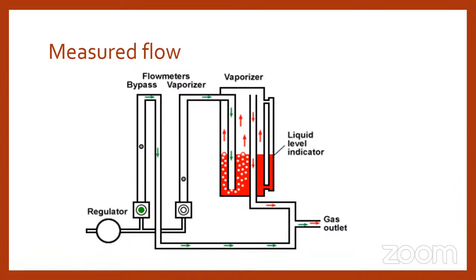So when we open this green knob, as you can see in the picture, the fresh gas enters this pipeline and goes directly to the patient. So we are bypassing the vaporizer and only giving the fresh gas to the patient.